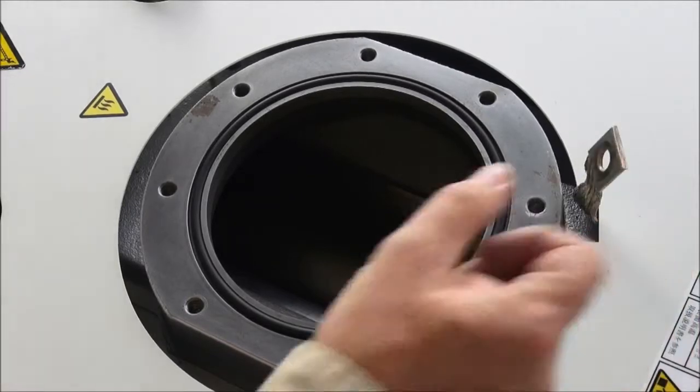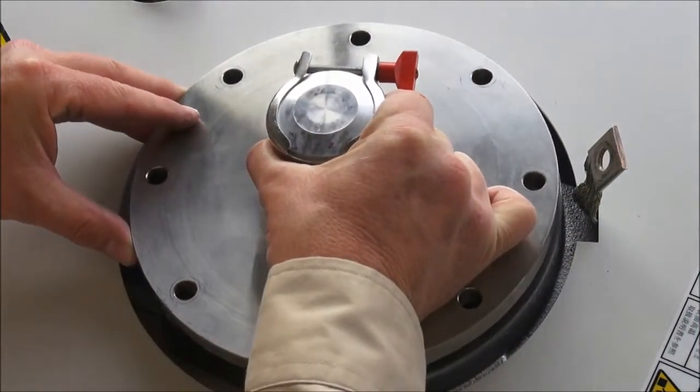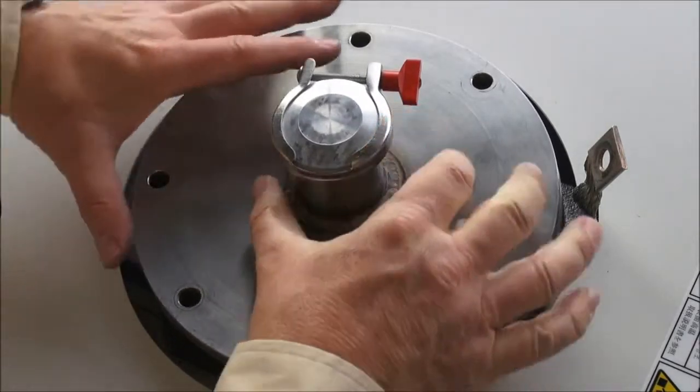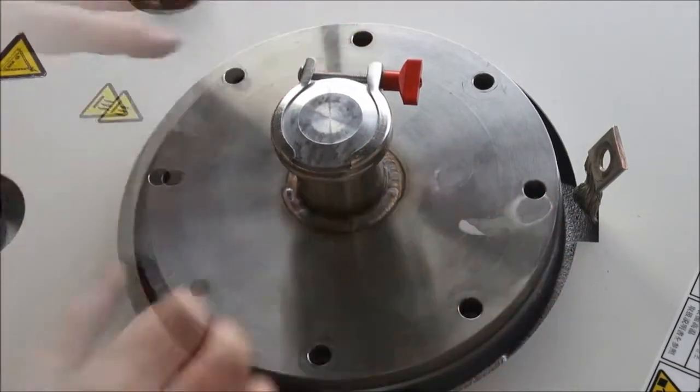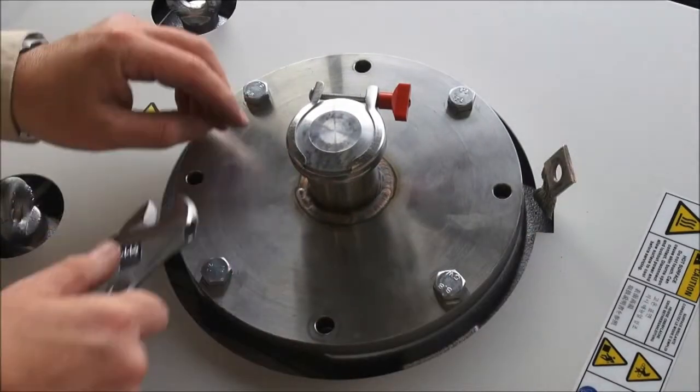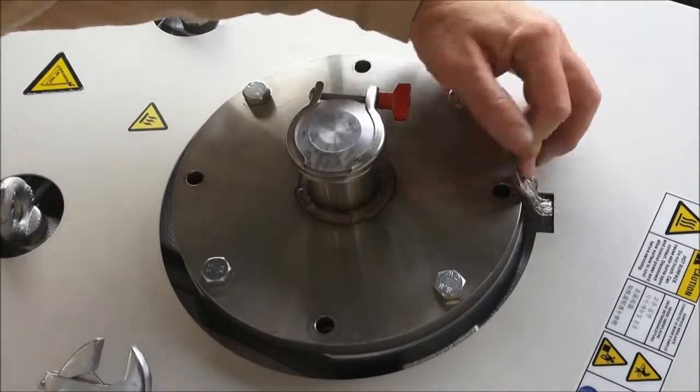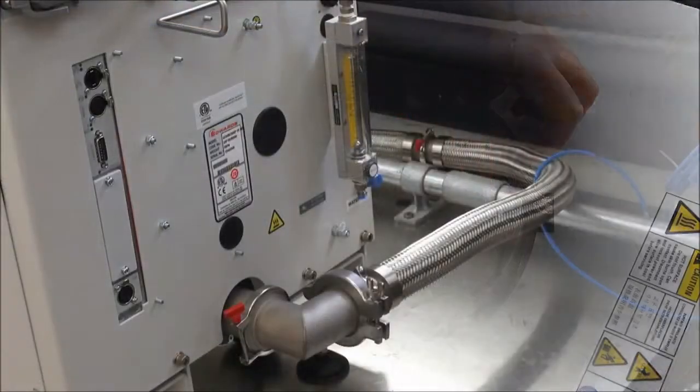There is an earth bonding strap next to the inlet which should be used to earth or ground the pump to the incoming vacuum connection metalwork. Carefully locate your inlet flange and use appropriate fixings to make sure it is correctly mounted, mechanically secure and fully vacuum tight. The earth ground strap should be attached using one of the bolts.